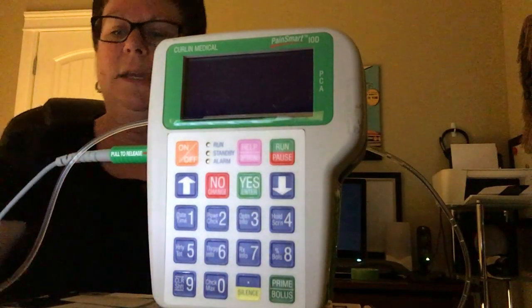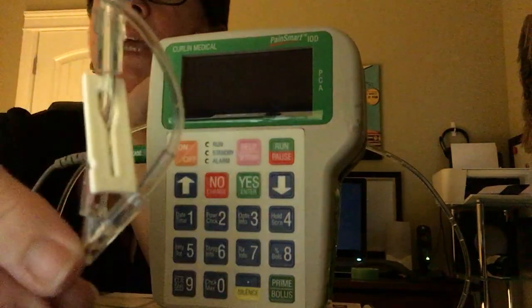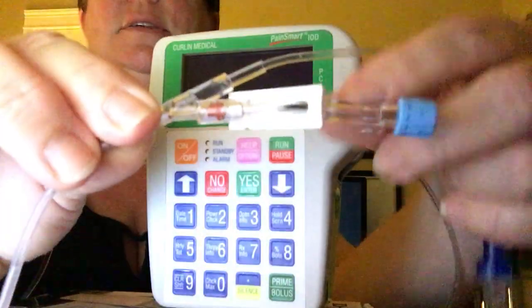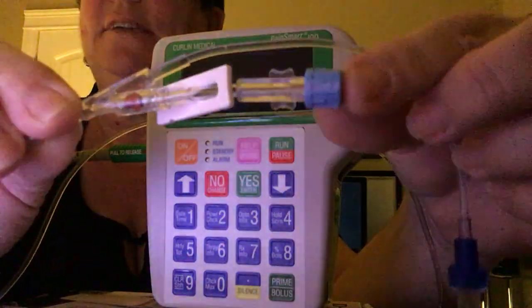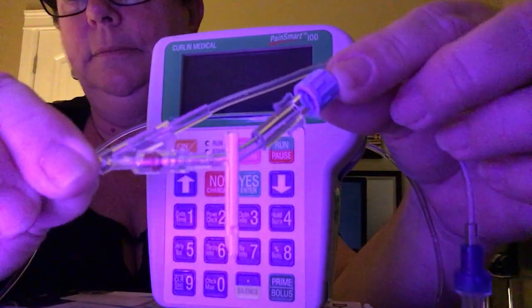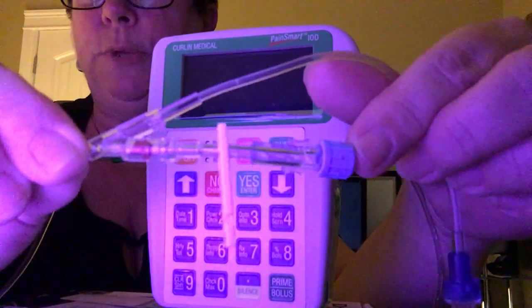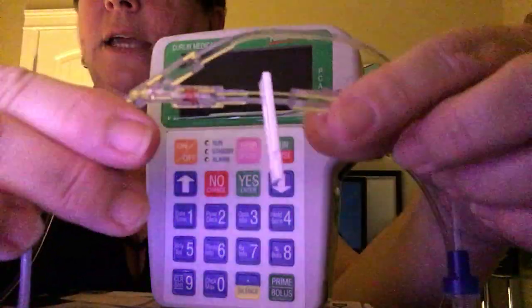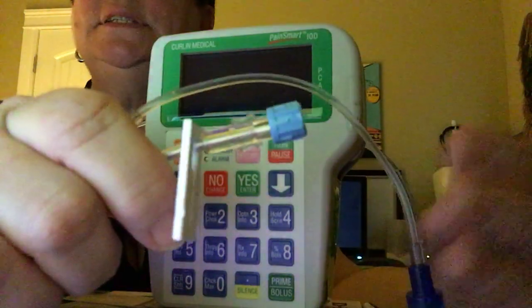The PCA tubing is also unique in that it has a Y already connected to it. So you are going to connect your safety line to here, which is the opposite of what we do now. Normally this would be the safety line and the drug would piggyback. The opposite is true. You're going to prime the tubing with narcotic all the way down to the end, and this will attach to the patient. So just attach that to your saline lock. And this will have your continuous infusion.